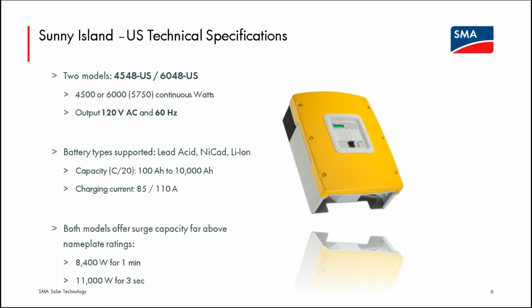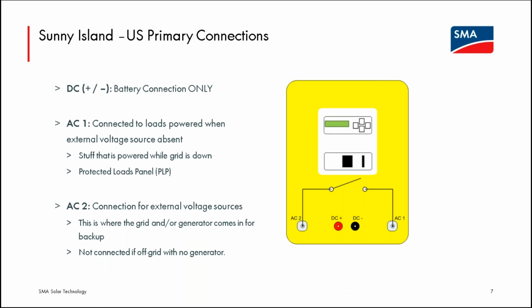That's almost triple the nameplate of the 4548 for 3 seconds. So plenty of excess capacity to provide that surge current to start critical loads like motors or pumps. I'm showing now a very simplistic view of the wiring of a Sunny Island, and we'll show the device circuitry actually with the lid off on the next slide.